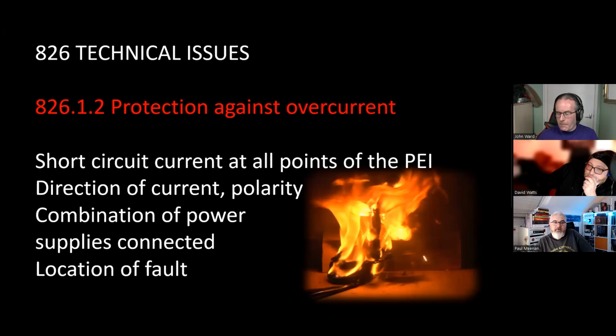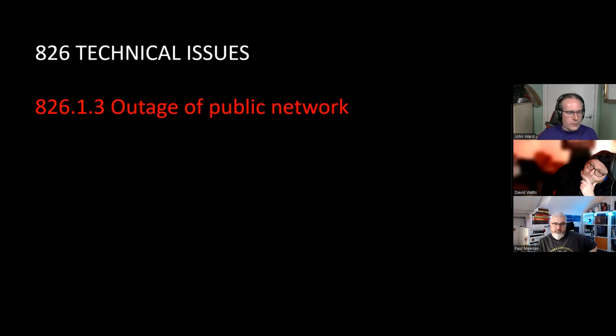Protection against overcurrent. You've got to consider your short circuit current at all points of the prosumer's electrical installation. So again, if it's from the grid, it's probably going to be quite high. If it's from battery storage, it could be completely different. There might not be enough to trip the relevant devices. The direction of the current can change, as can polarity. It could have a combination of things connected. You could have the grid on, and you could have your batteries on, and your solar coming in. So all of these different things, you're going to have current going in different directions. And also, where is the fault relative to the protective devices? Because if you've got power coming in from different directions, that protective device might not disconnect the actual source of where the current is coming from, as that may change depending on where your energy is being created or distributed.